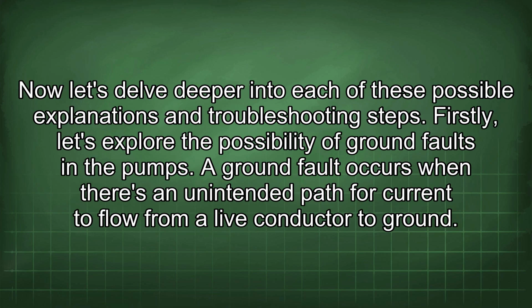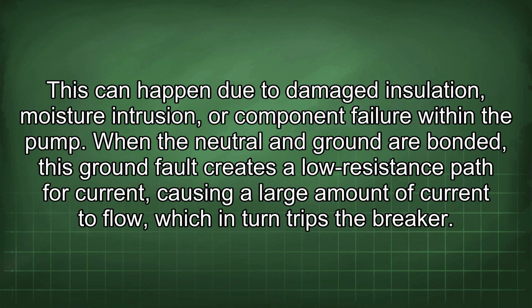Now let's delve deeper into each of these possible explanations and troubleshooting steps. Firstly, let's explore the possibility of ground faults in the pumps. A ground fault occurs when there's an unintended path for current to flow from a live conductor to ground. This can happen due to damaged insulation, moisture intrusion, or component failure within the pump. When the neutral and ground are bonded, this ground fault creates a low resistance path for current, causing a large amount of current to flow, which in turn trips the breaker.